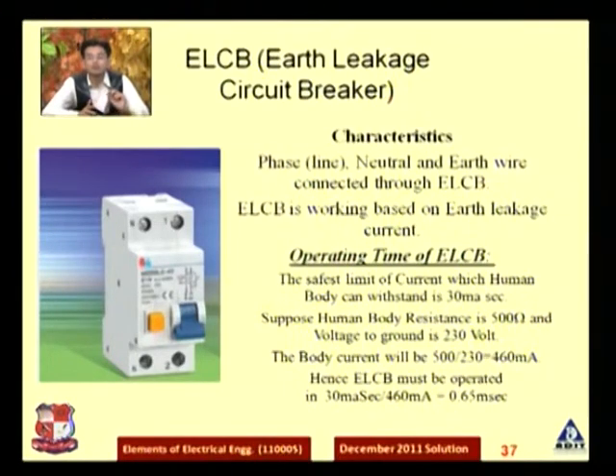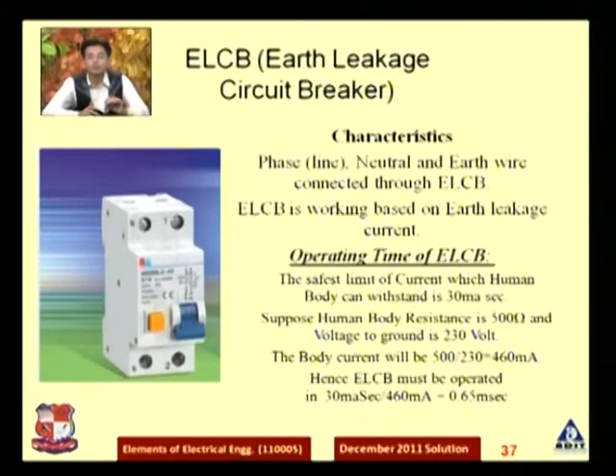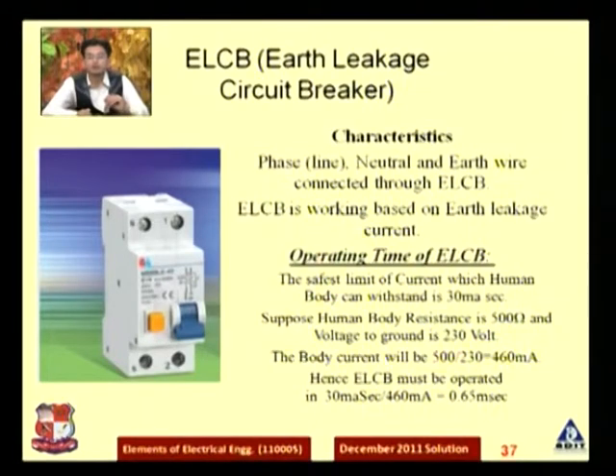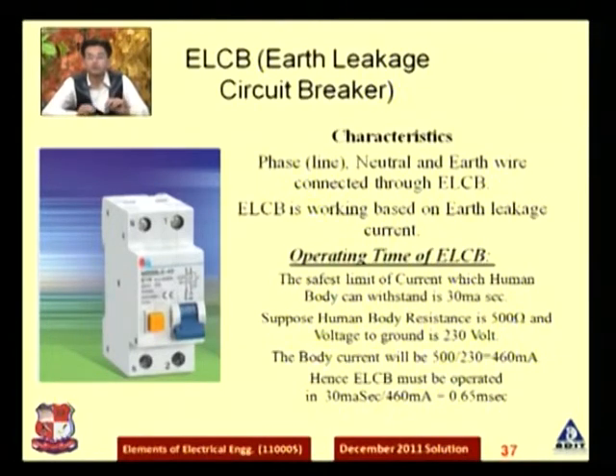The operating time of ELCB: the safe limit of current the human body can withstand is 30 milliampere-second. ELCB should operate before that limit. Suppose human body resistance is 500 ohms and voltage to ground is 230 volts (standard in India). The body current will be 230 divided by 500, which gives 460 milliampere. So ELCB must operate in 30 milliampere-second divided by 460 milliampere, which equals 0.065 seconds — that is 65 milliseconds, meaning the operating characteristic of ELCB is very fast.